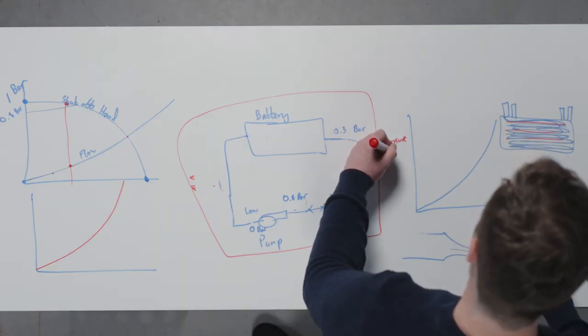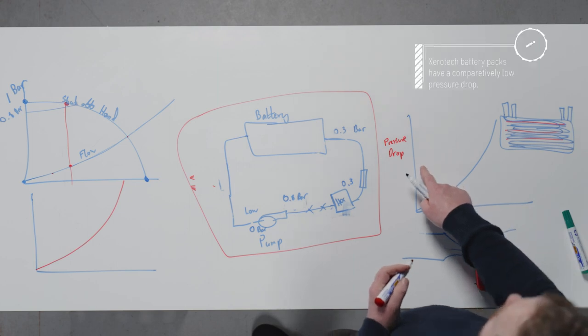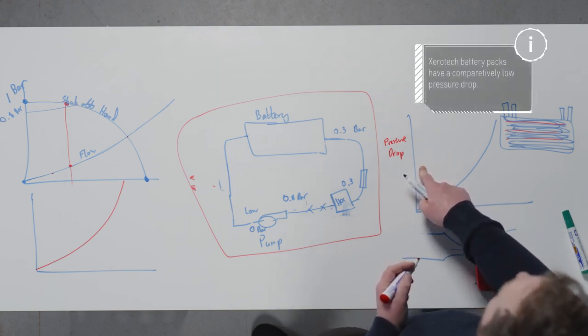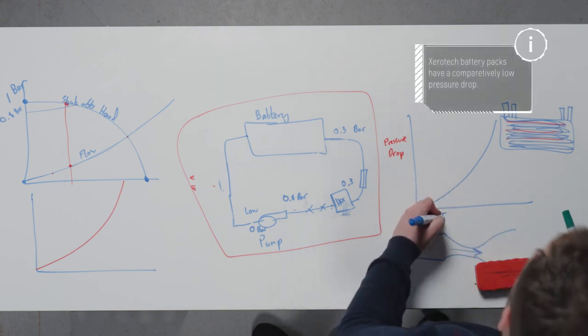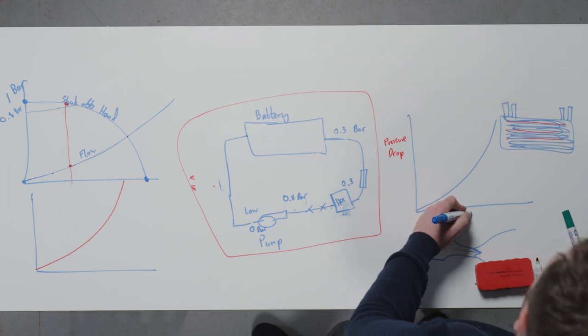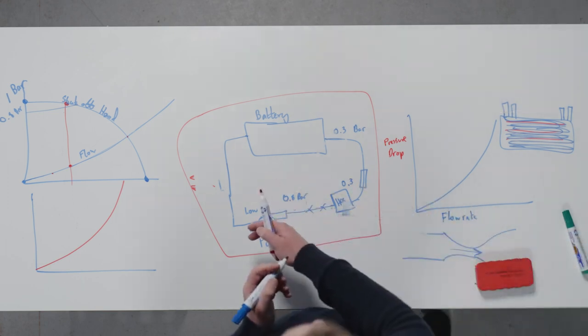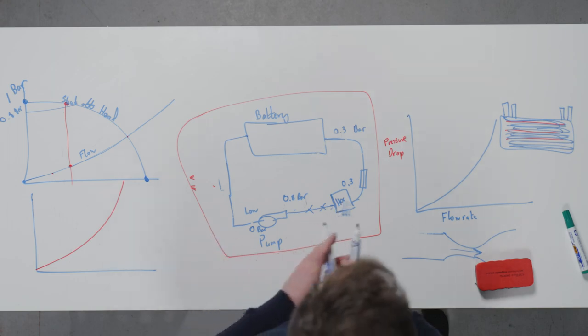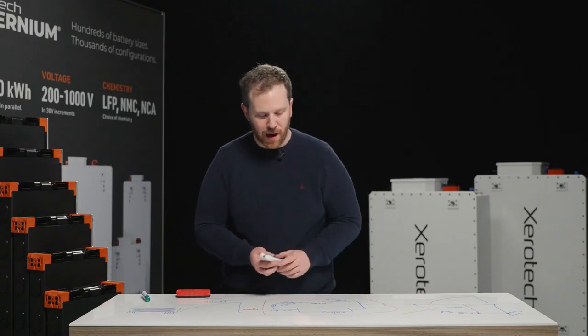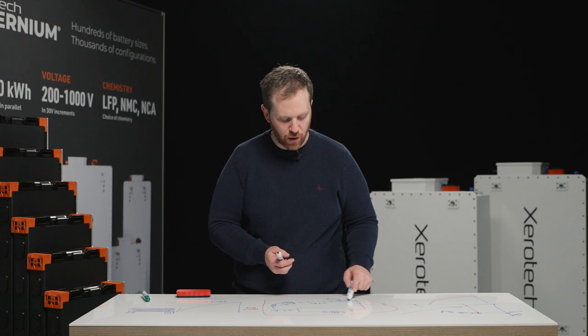And what's unique about Xerotech batteries is the pressure drop is really low. It's very low compared to other battery packs on the market, which means that you can develop very, very high flow rates through the pack with a typical pump. It's very important for Xerotech batteries to be at the end of the cooling circuit.